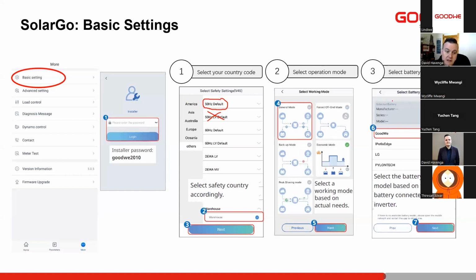Next, we'll select our working mode. You have general mode, which is the default. That is designed for most self-consumption. Next is backup mode. The backup mode is used to essentially keep our batteries full. It will always keep the batteries full and only discharge when the grid fails. That also charges the batteries like a UPS, so it is a slow charge on the batteries to always keep them full.